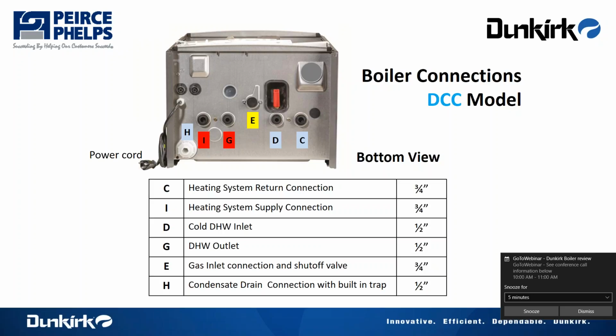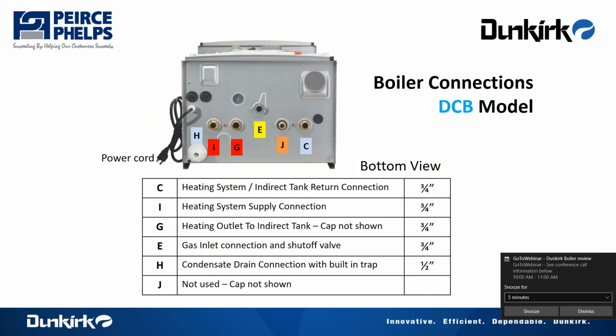Letter H is the condensate removal system, a nice sophisticated drain trap that catches both condensate off the venting system and also condensate off the heat exchanger itself, and that's your drain point there to run off either into a filter or down to a drain. E is the gas connection, 3/4 inch gas inlet. This shows the straight heat boiler, same connections, I and C, system supply and return. Letter G is supplying hot water down to the indirect. Of course, J we wouldn't be utilizing. That would be hot water coming out of the indirect. And E would be the gas connection, condensate removal off letter H.